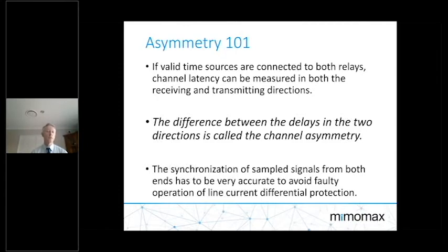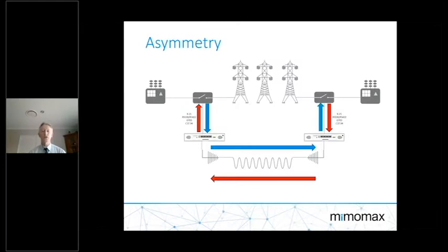across the channel. So the difference between the delays in the two directions is called channel asymmetry, and that has to be quite accurate, otherwise we can introduce faulty operation or false triggering of the protection circuits. So here's just an image of where those asymmetries can sometimes sit, and often it is across the communications network that we're trying to utilize to compare and then trigger the relay. So it is important that we minimize asymmetry in both directions.